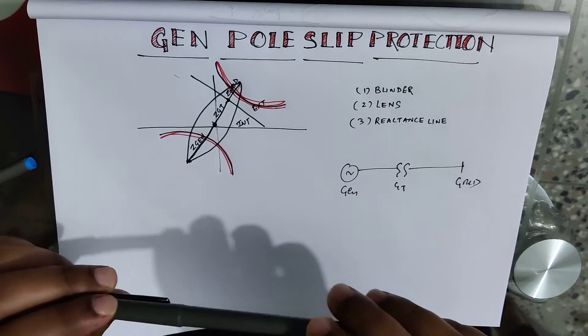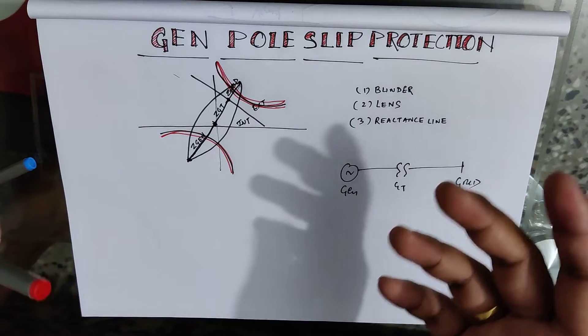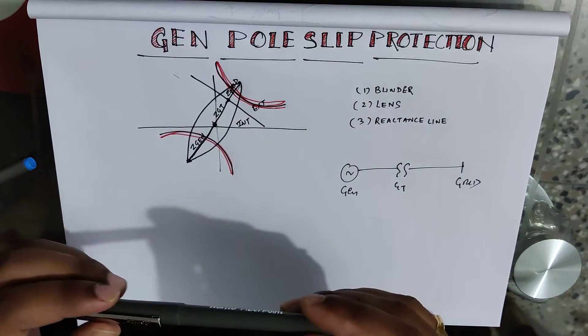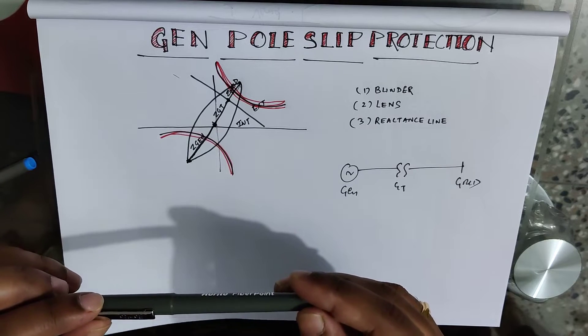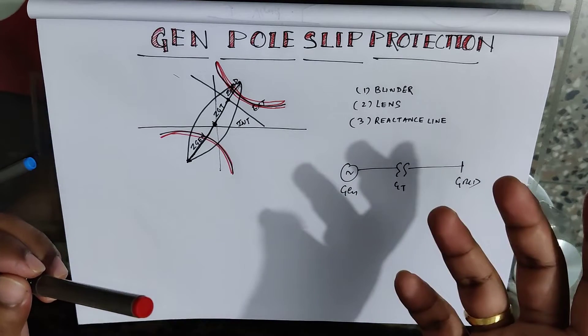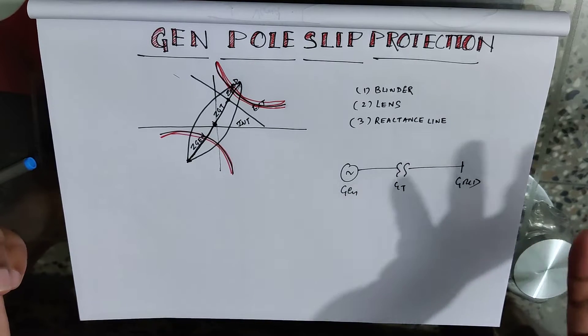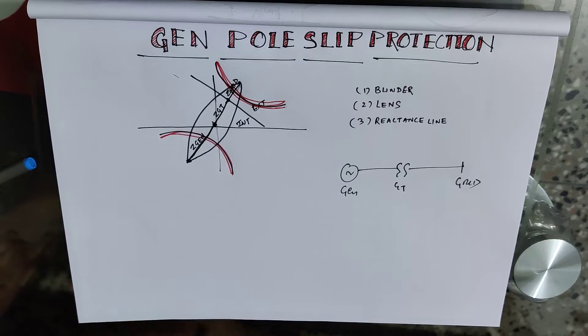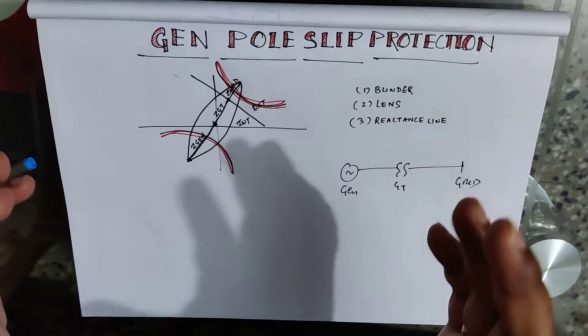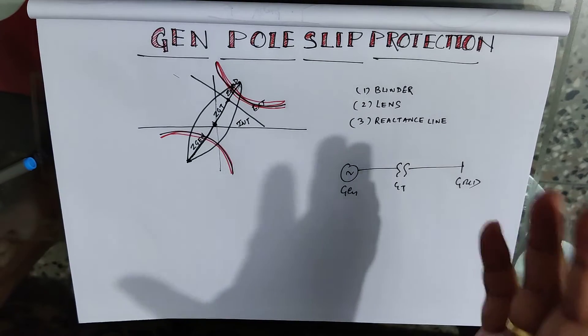As I explained in the last video, pole slip means losing synchronism. The generator rotor accelerates, over-speeds, and loses synchronism with the grid. Due to over-speed, the frequency generated at the terminal voltage is higher than the desired one, and that voltage is injected into the grid, so the grid voltage will also get affected. The other generators connected to the same grid will sense that frequency, and accordingly their governor will act and their speed will also get disturbed. So it is better to isolate the faulty generator as soon as possible to avoid a blackout condition.